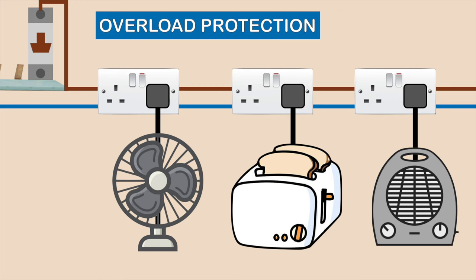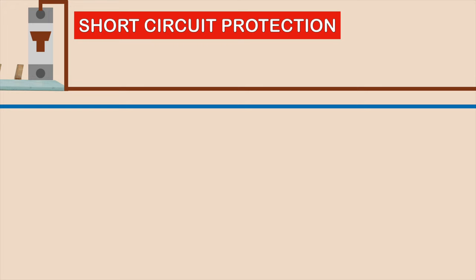The other safety feature is short circuit protection. If the live wire was to bypass the load and touch the neutral, there is next to no resistance within the circuit and you end up with an instantaneous and large current flowing through the wires. This increasing current will create a large magnetic field within the MCB which will trip the MCB to protect itself and the cable.